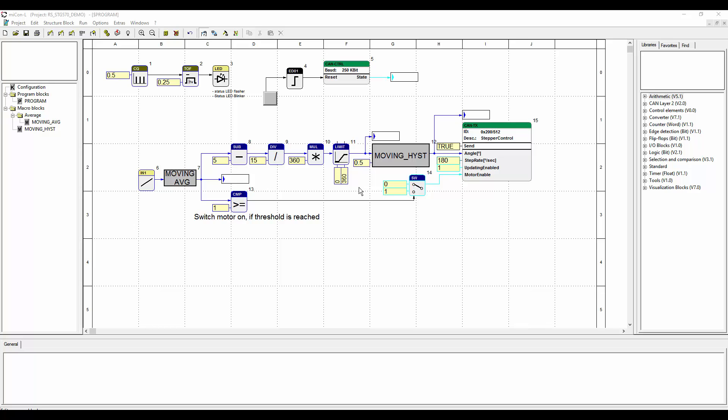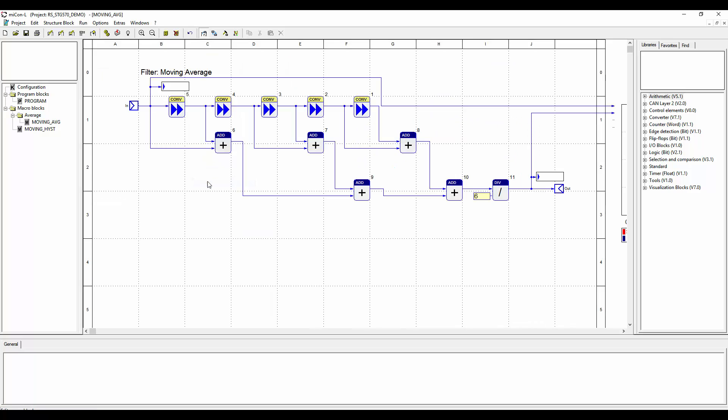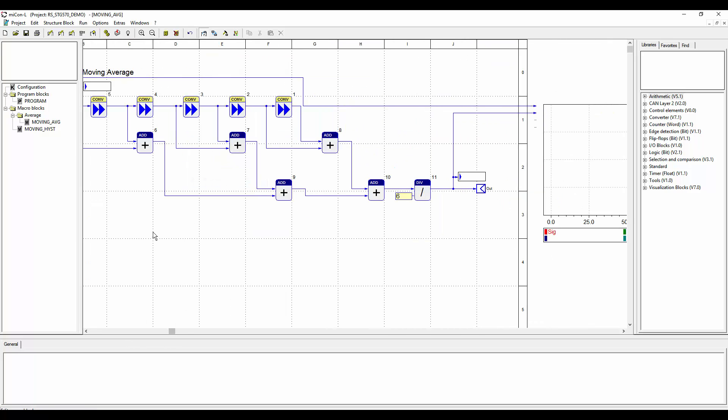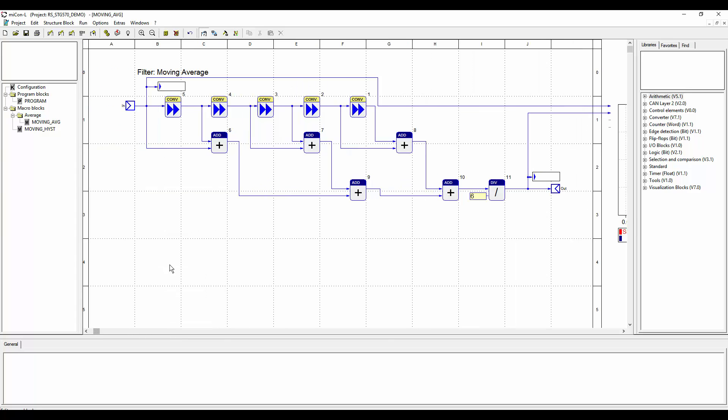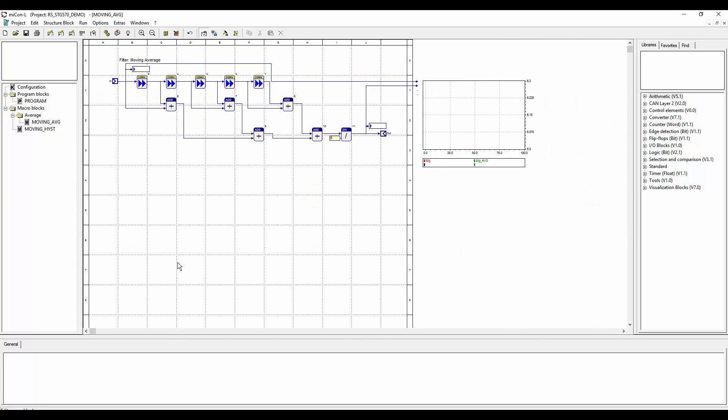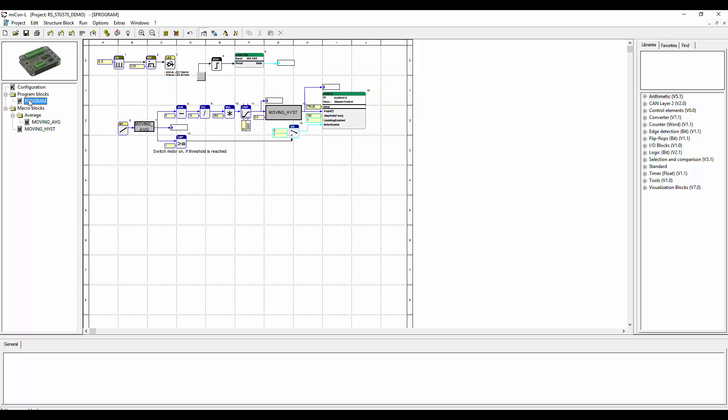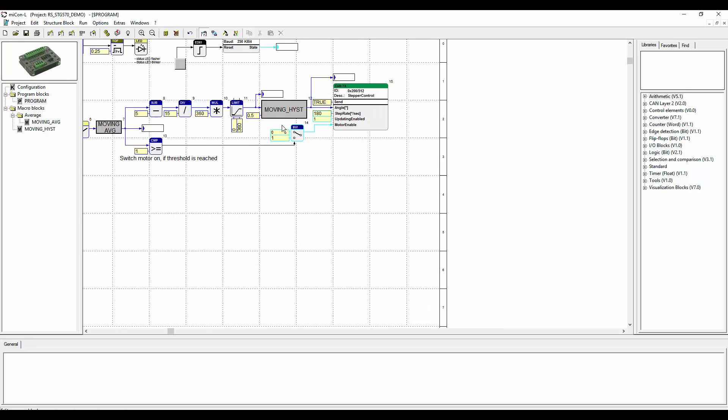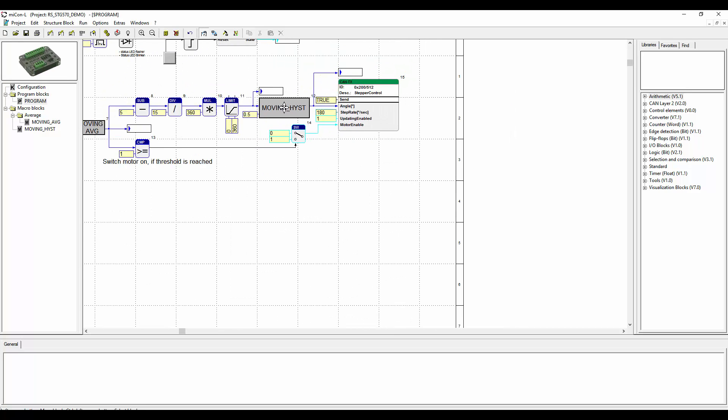Now to achieve a more stable value for that calculation process, we implemented a macro block called moving average. With that average, we clear out the jittering of the input value a little bit. Unfortunately, there was still some fluctuation. So next we calculated a hysteresis in the macro block moving hysteresis, which is right before the CAN send function block.